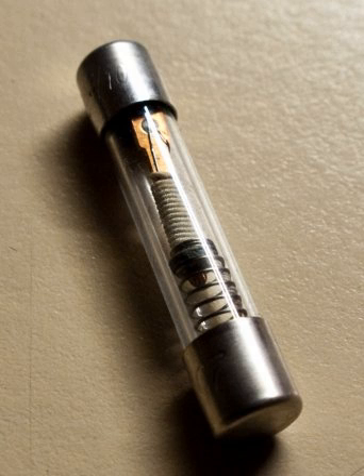To prevent installation of fuses with an excessive current rating, later fuse boxes included rejection features in the fuse holder socket, commonly known as rejection base type S fuses, which have smaller diameters that vary depending on the rating of the fuse. This means that fuses can only be replaced by the preset type S fuse rating.